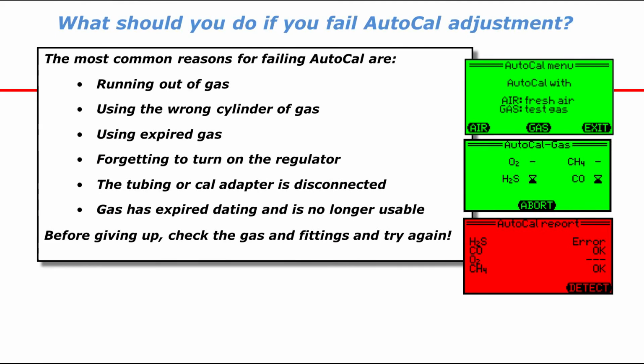Instruments that fail autocal may not be put into service until the failure condition is corrected. The autocal report screen will indicate which sensors are affected by the failure condition. The most common reasons for failing autocal are running out of gas, using the wrong cylinder of gas, using expired gas, forgetting to turn the regulator on, or the tube connecting the regulator to the calibration adapter has become disconnected. If the report shows that multiple sensors have failed, the problem is usually one of these conditions.